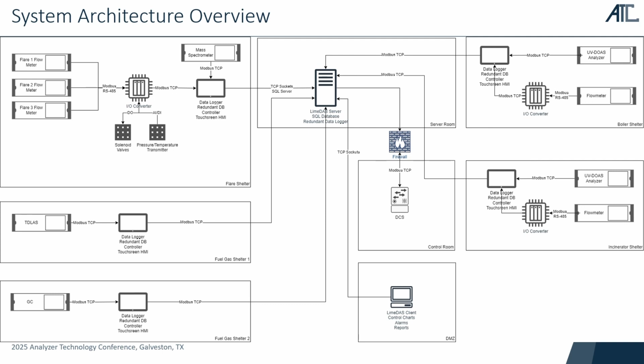So when we talk about the data collection unit, the data logger, you can think of it as a newer take on the PLCs, and we designed it to be more robust and easier to maintain than the typical PLC setup. However, it can still communicate with various PLCs as required based on the facility. Then you can see various shelters. If we started at the top left, that would be, in this example, a flare shelter. Then we have a fuel gas shelter. One had a TDL system, one had a GC system. And then the top right, we have a boiler stack and an SRU stack as an example with similar setups. And various stacks, various shelters have various instruments on them.